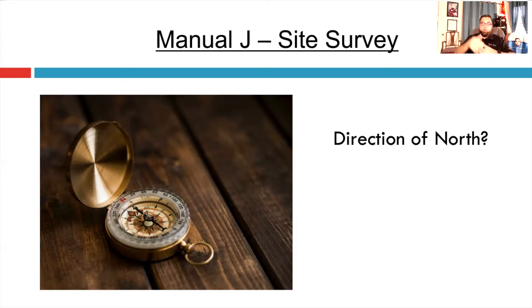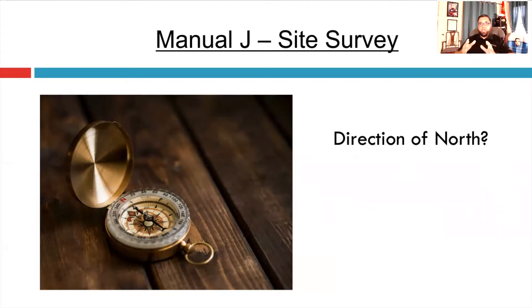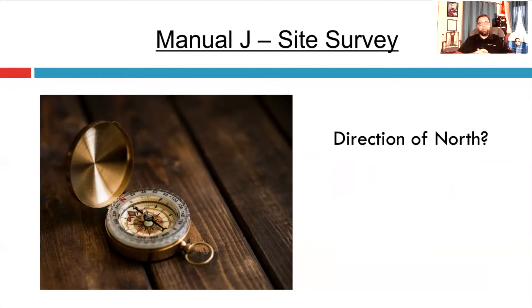North always pops up facing north on Google Maps, and you can verify which way that floor plan is facing. It does impact the load, so it's really important. Make sure people are actually getting the correct direction, not the direction that provides the highest load. I've seen people change the compass in Wrightsoft and just go with the highest, which is not correct. We want to get the real loads for that home, and in order to verify it, we have to have that right.